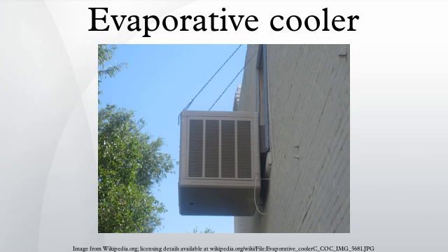Indirect evaporative cooling is similar to direct evaporative cooling but uses some type of heat exchanger. The cooled moist air never comes in direct contact with the conditioned air. The moist air stream is released outside or used to cool other external devices such as solar cells, which are more efficient if kept cool. One indirect cooler manufacturer uses the so-called Maisotsenko cycle, which employs an iterative heat exchanger that can reduce the temperature to below the wet bulb temperature.